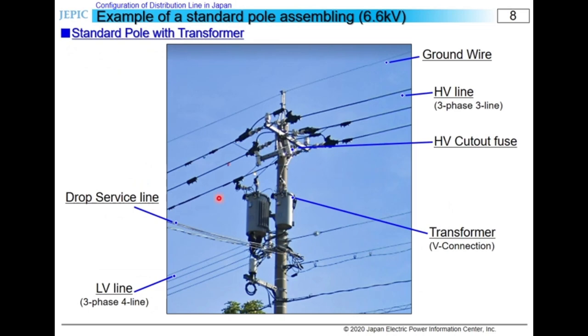This picture is an example of a 6.6 kV standard electric pole with transformer in Hokuriku region. Basically, the equipment with higher voltage is assembled so that it comes to the higher position. I'll explain about the equipment used for power distribution from the next slide.